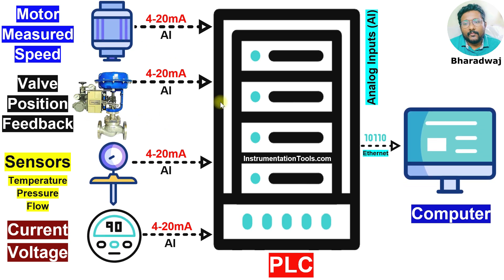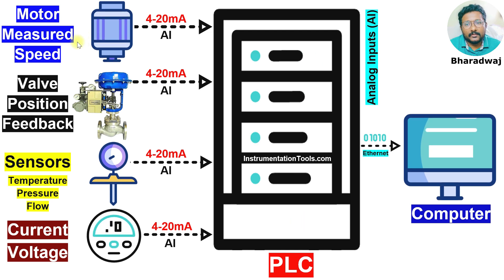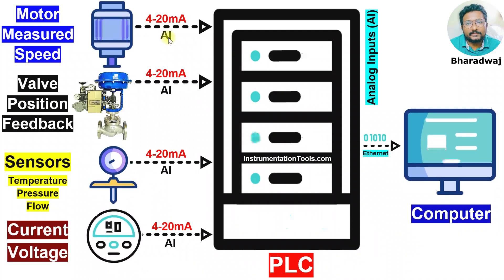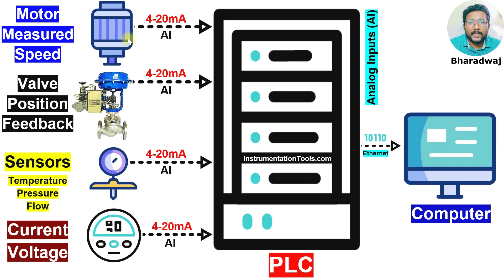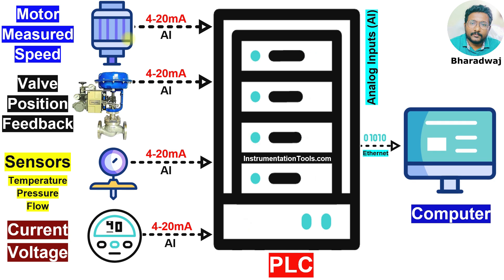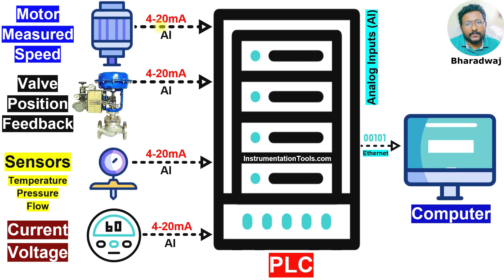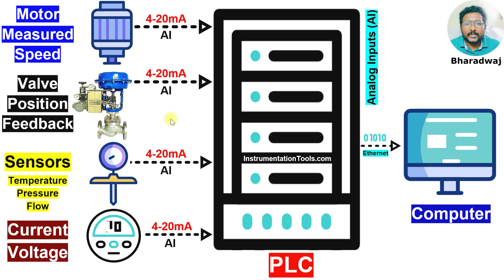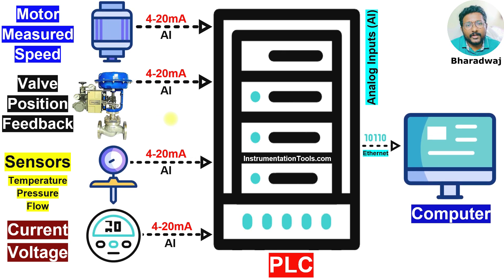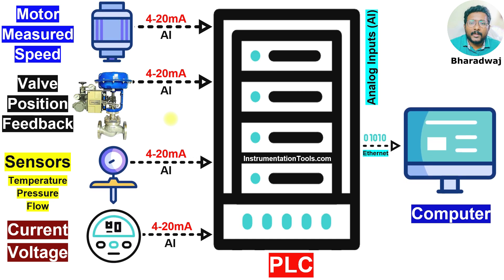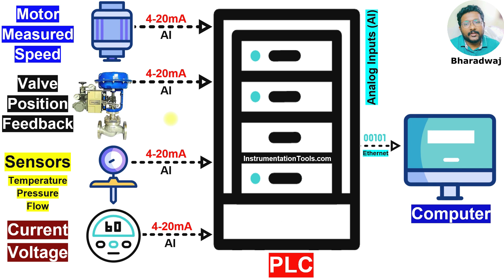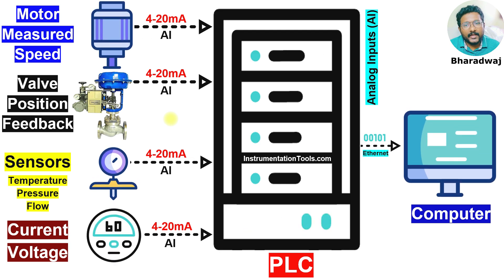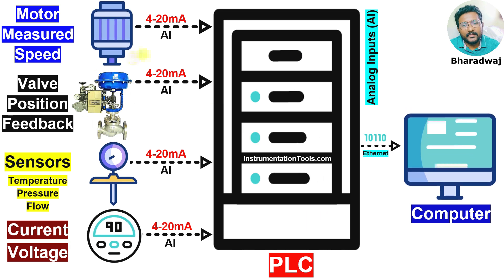Let's say the motor speed is 0%, 0 RPM — then the PLC receives a 4 mA signal. Let's say the motor speed maximum is 1000 RPM — then the PLC receives 20 mA. The zero scale is 4 mA and the full scale is 20 mA. Your measurement may be in any range, any unit. The transmitter or device calculates the equivalent current signal and sends it to the PLC.